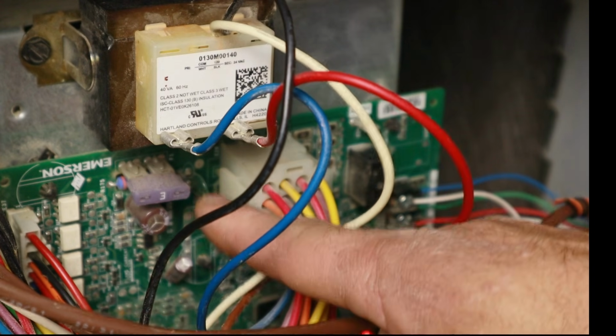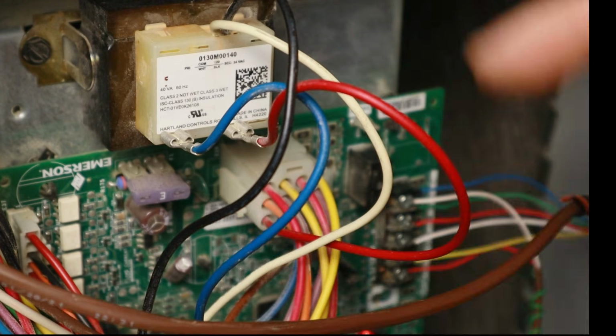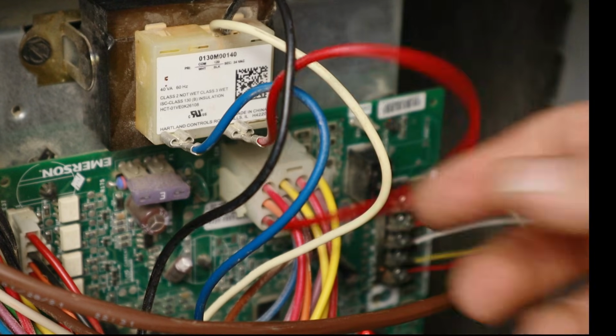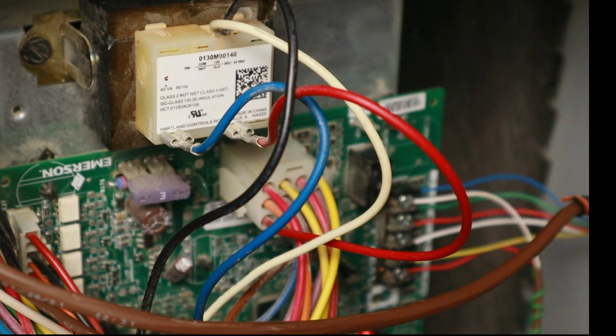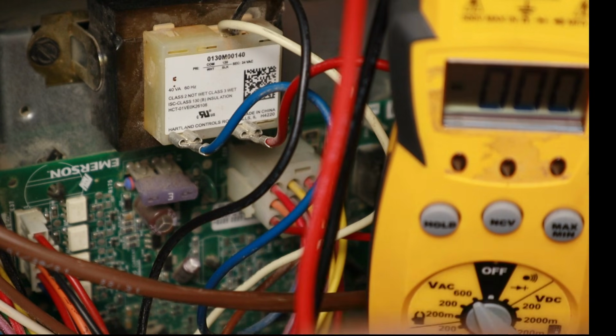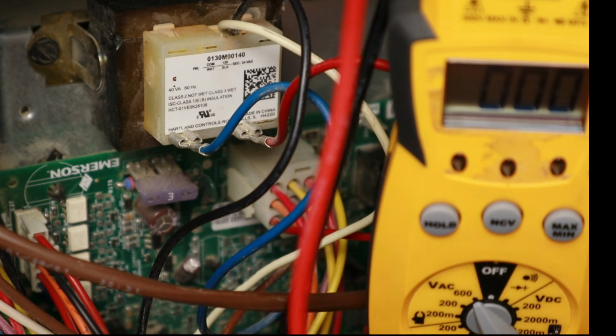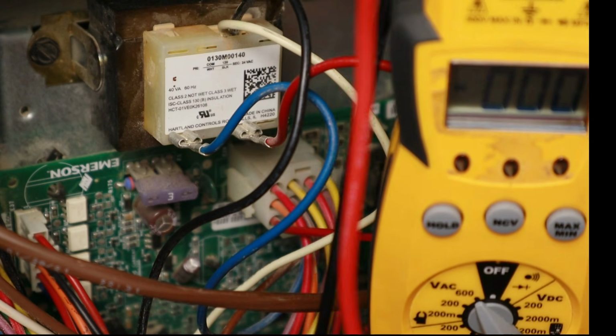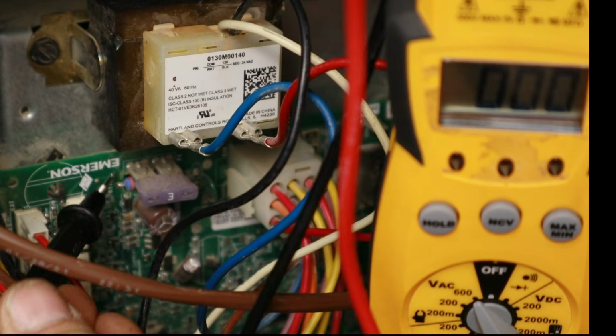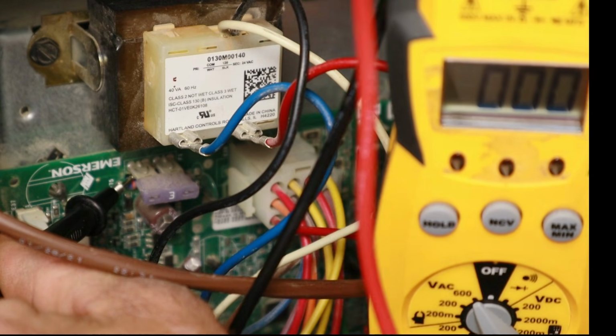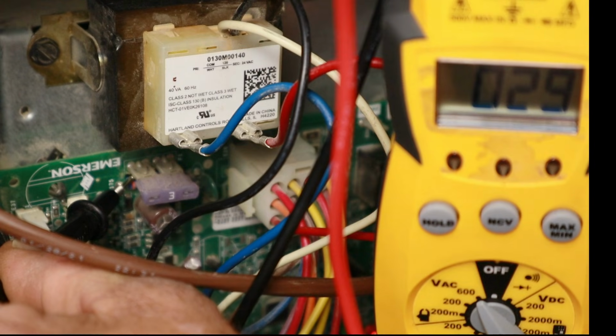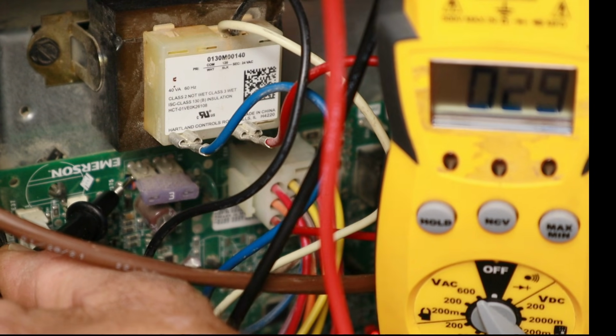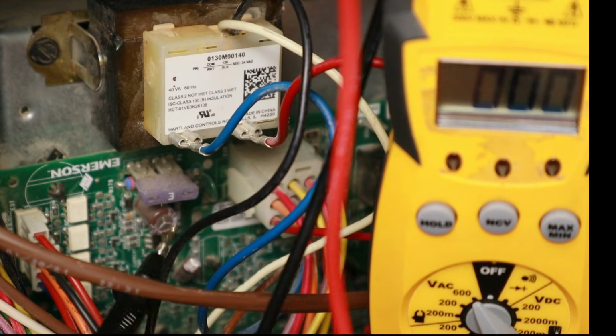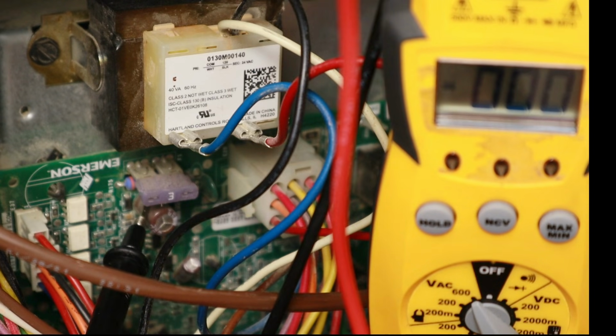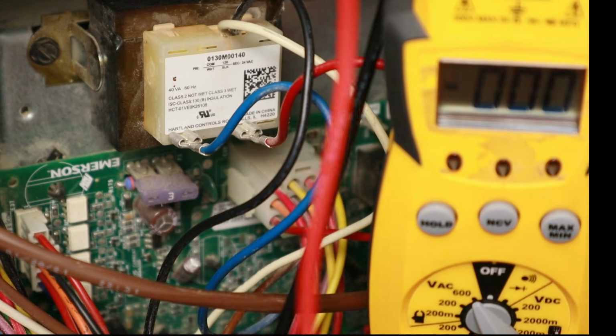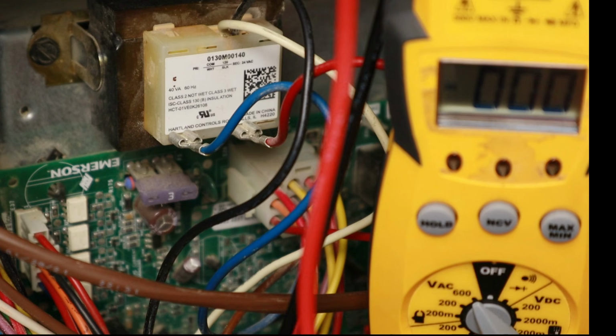If I was not reading 24 volts on this fuse, but I'm reading it coming out of the transformer, I could have a bad Molex plug connection here. Once the power makes it to the fuse, it's got to go through the fuse to carry on. So to make sure we actually have a good fuse, we now want to test the other side of that fuse, all right, and see what we got there. And we are reading 29 volts. So we know we got a good fuse. If I was reading voltage on one side, but not on the other, you could have a blown fuse, and you just take that out, hold it up to the light, and see if it's blown.